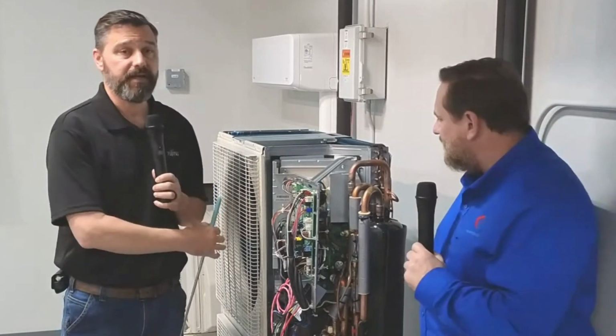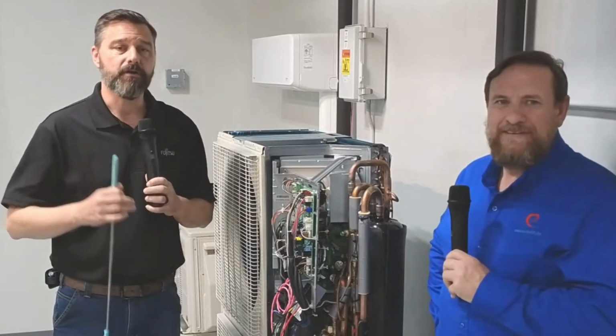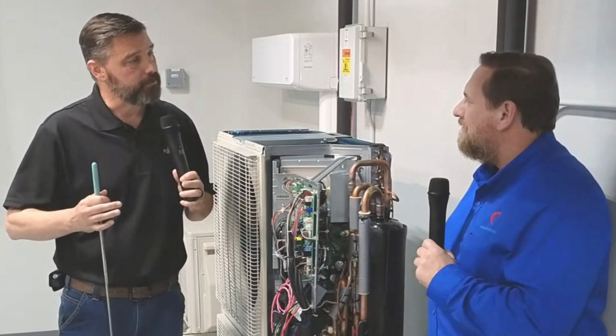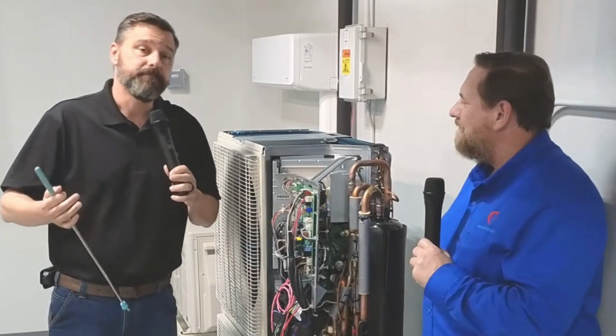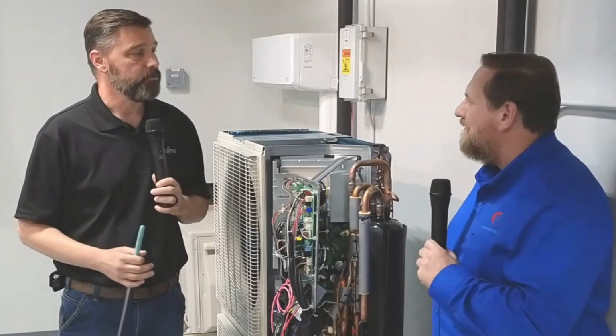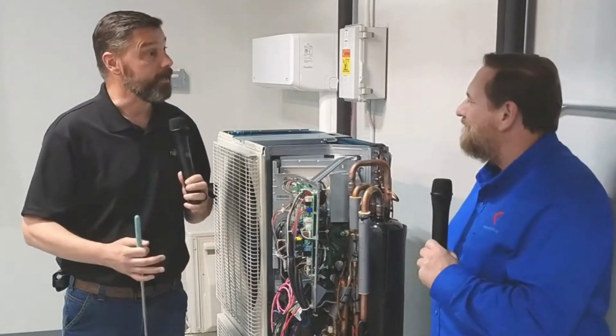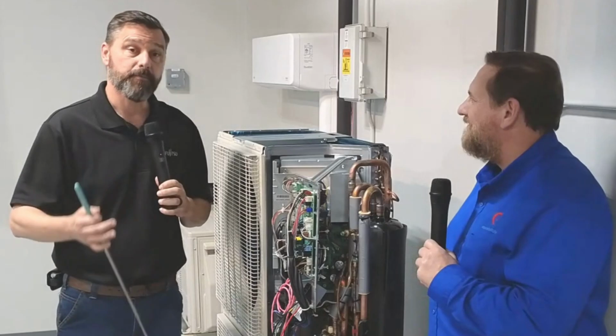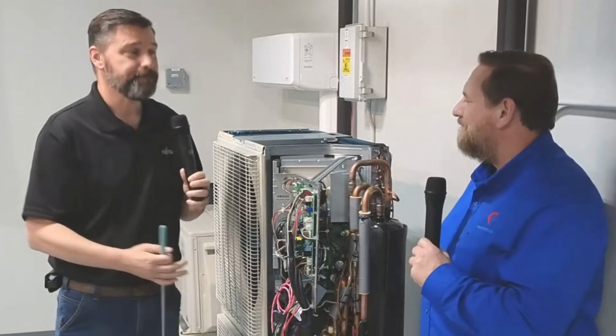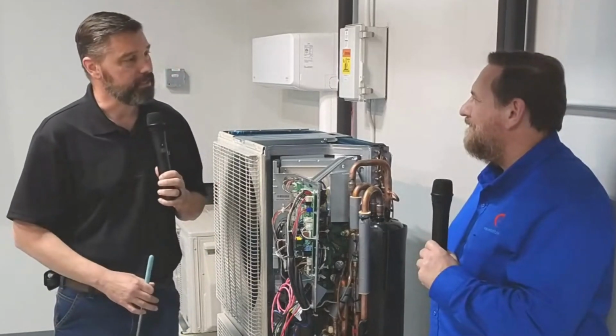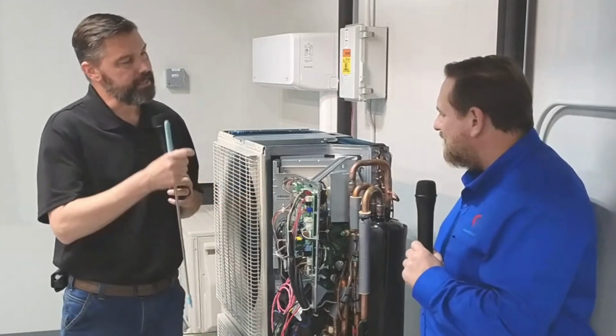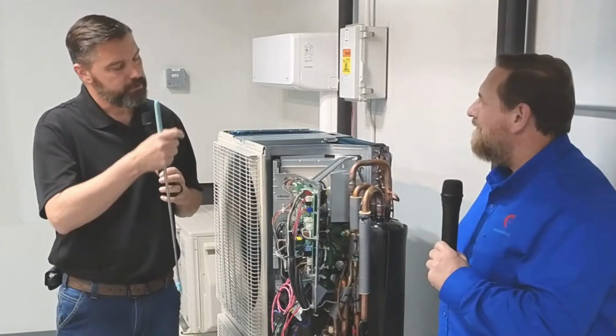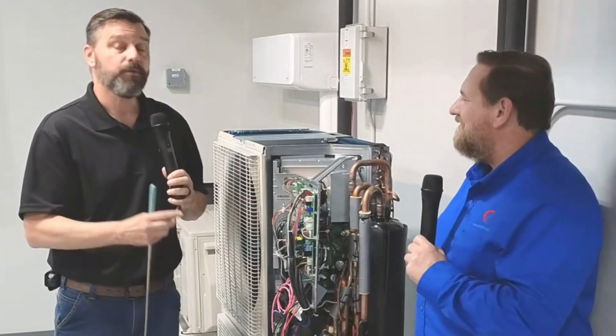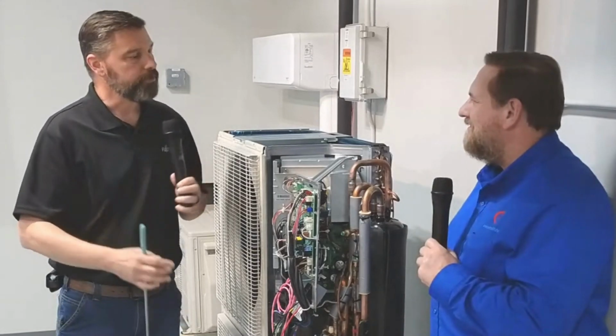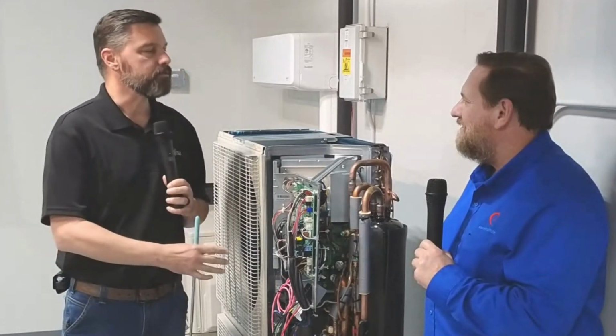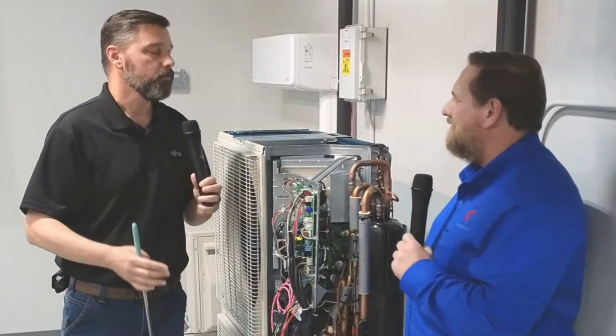We can look at things like fan speed and then look at the charts and graphs and say, okay, are we within normal operating fan range or are we running high on the fan? If our fan's overamping or running too high, we can go back and look at, okay, why? Why are we trying to move excessive air? Is our compressor too hot? Do we have a low charge? 90% of the time, that's the issue that we're looking at. So having the ability to look at that 7-segment LED and read all these different points in the system without having to hook up gauges, we really get a good understanding of what the system is trying to do and what it's actually doing.